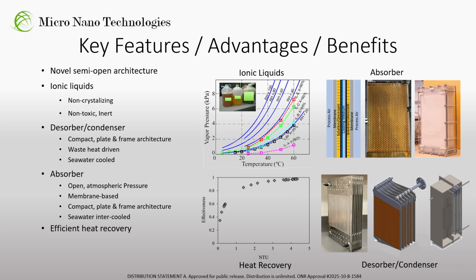The intercooled multiplate absorber provides a large surface area with minimal pressure drop to support the dehumidification of the ventilation airstream. A thin film of ionic liquid, constrained by hydrophobic membranes permeable to water vapor, flows across the outer surfaces of each absorber plate. As the water vapor is absorbed by the ionic liquid, the heat released is absorbed into cooling water within each plate. This immediate removal of the heat increases the system dehumidification performance, and depending on the cooling water temperature and flow rate, provides the ability to cool the ventilation air.